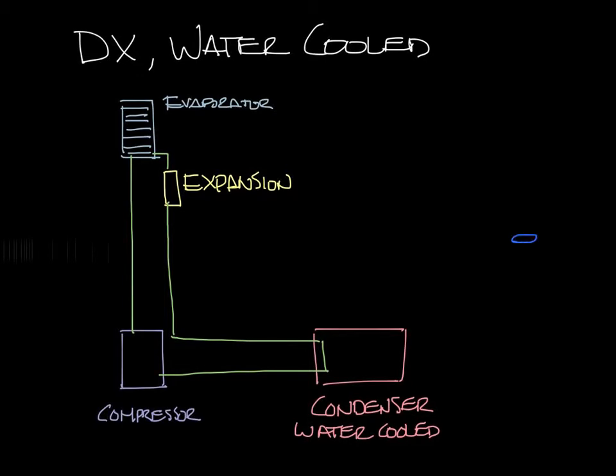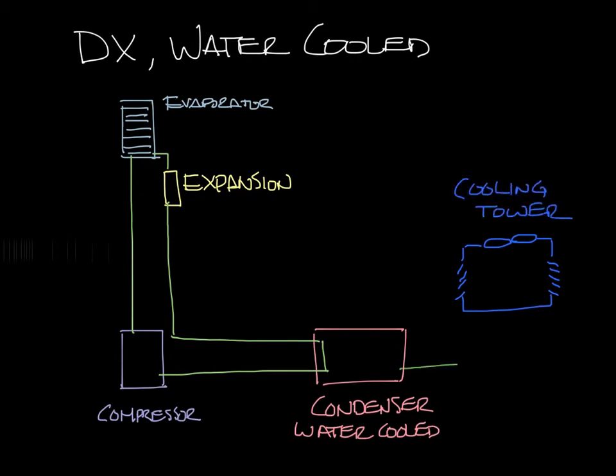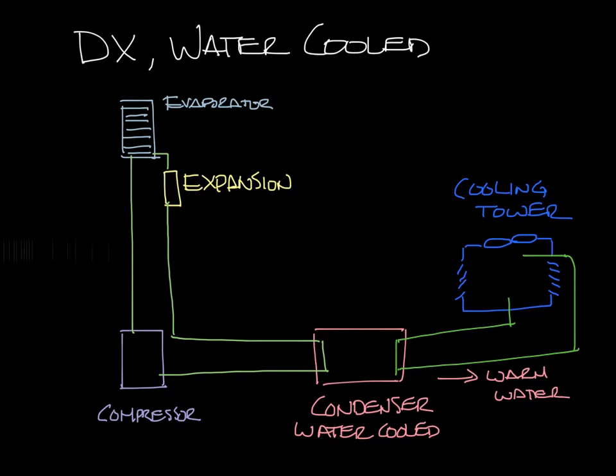In our water-cooled system, you also need a cooling tower. The water that is heated up in the condenser travels to the cooling tower. The cooling tower has a fan to draw air across water from the condenser. This causes some of the water to evaporate and cool, and the water falls to the bottom of the tower to the sump, and that water goes back to the condenser to start the process all over again.